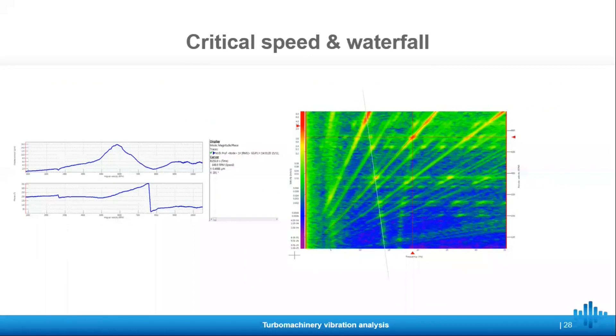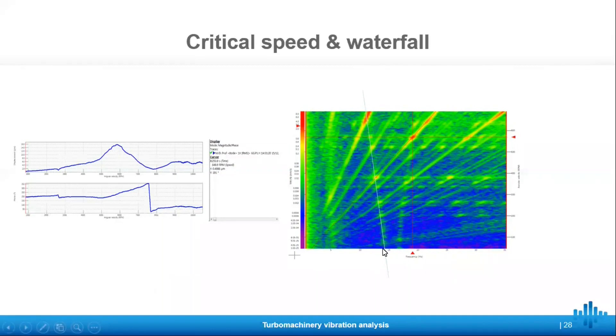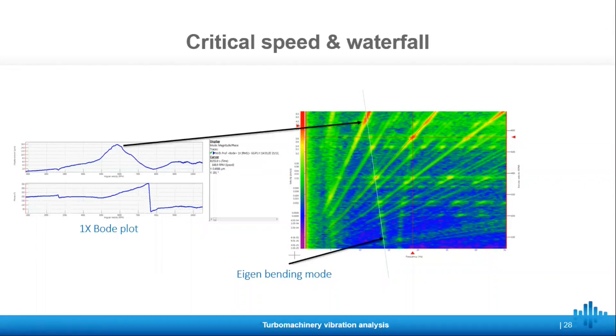Let's take a look at the link between the Bode plot and the waterfall. The Bode plot is a trend of the 1x values — a 2D or scalar graph plotted versus speed. The waterfall collects spectra versus either speed or time, with the vertical axis or color representing the magnitude. With the logarithmic scale, it's easy to see vertical lines which represent a frequency that is always present, or diagonal lines which are the orders. When these two cross, you end up with a resonance. So if we see any resonance in the Bode plot, we will be able to see the corresponding resonance in the waterfall.